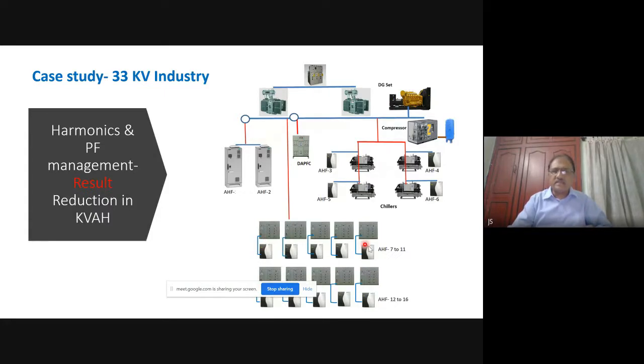When we did this exercise, that means there are 10 numbers of 60 ampere active harmonic filters, 4 numbers of 60 ampere active harmonic filters for the VFD driven chillers, and 2 numbers of 300 ampere active harmonic filters. Since they already had one level of harmonic filtering avoiding harmonic amplification, we resorted to the active harmonic filter to prevent parallel branch circuits from being infected by the circulating harmonics.